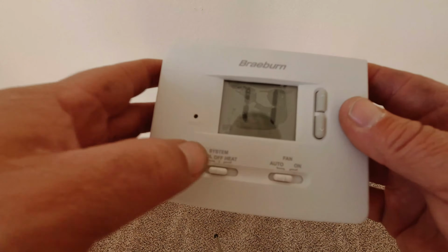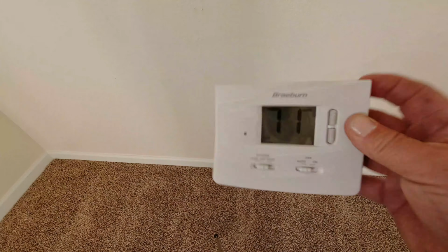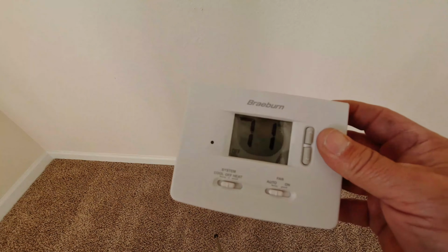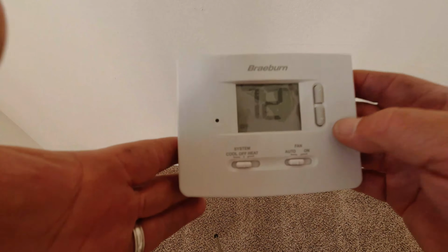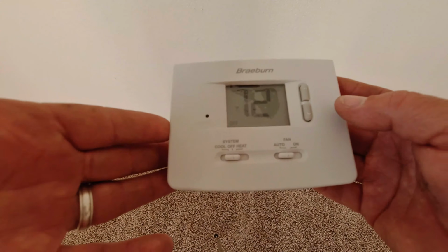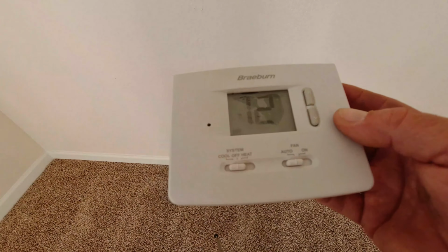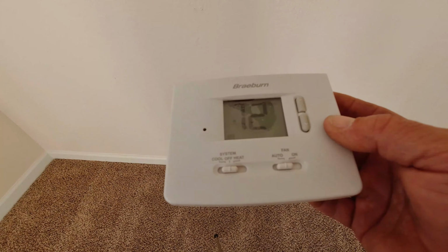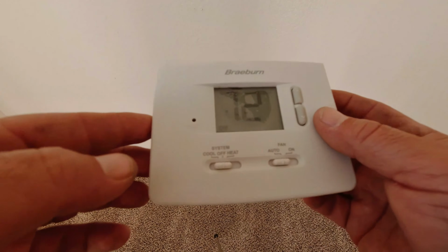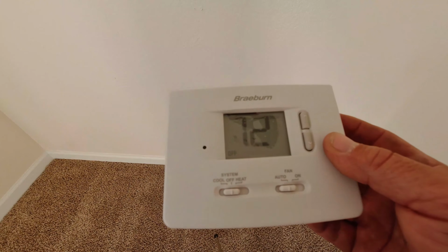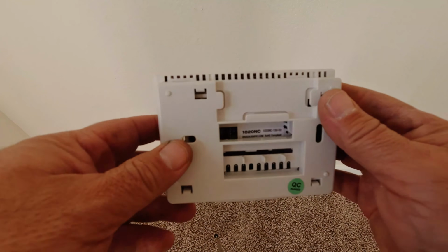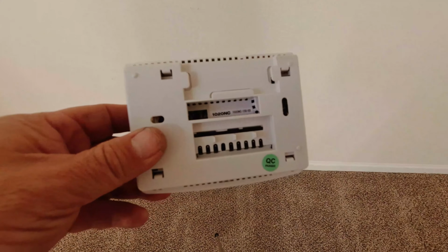They do not make the air conditioner blow colder or hotter. All they do is send the signal for heat or for cold, and that's all they do. They don't do anything else. Some people say, well, I don't think the thermostat is good because it's not blowing cold enough. Well, it's got nothing to do with that. All it's doing is reading temperatures, and it's really just bridging the 24 volts over to the heater or to the air conditioner, whatever it's calling for. That's all it's doing, and it's engaging. But it does not send a signal for hotter or colder air, nothing like that. It just bridges a signal, and that's all a thermostat is doing. This is really important to understand first.